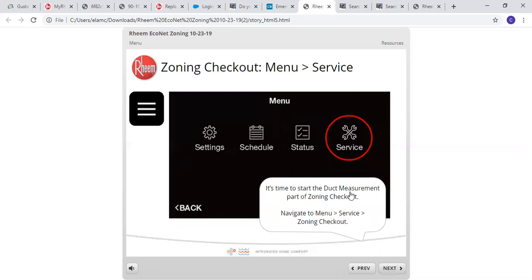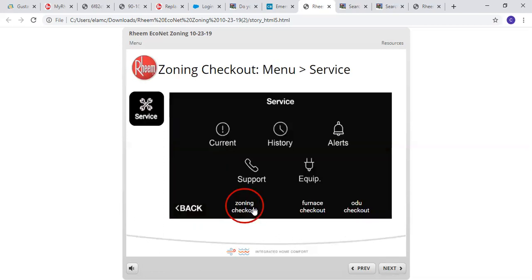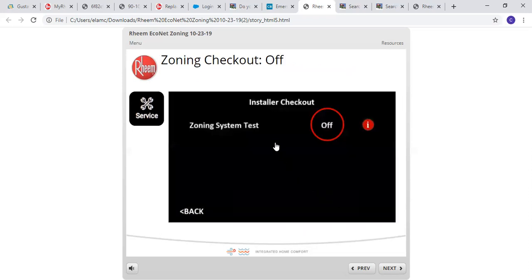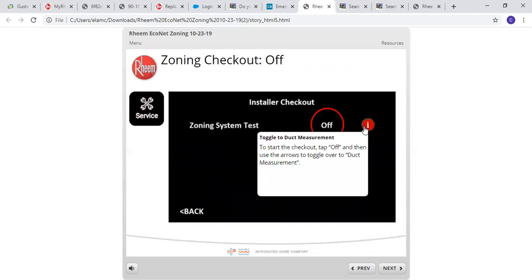Okay, so it's time to start the duct measurement part of the zoning checkout. We'll go into the service, zoning checkout. Now here we have the options. So we're in service here. If you want to check out just your furnace by itself in the future, click on furnace checkout. If you have an inverter system and you want to check it out in high cool or high heat, go in here and do that as well. Here, your zoning checkout. Click that. We do want to do a zoning test, so we can turn that on. To start the checkout, tap off, and then use the arrows to toggle over duct measurement.